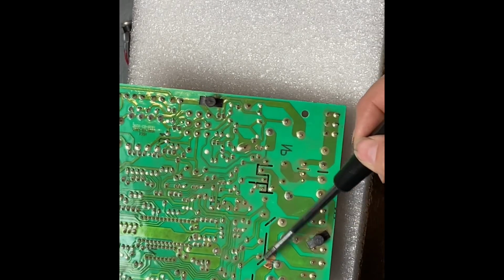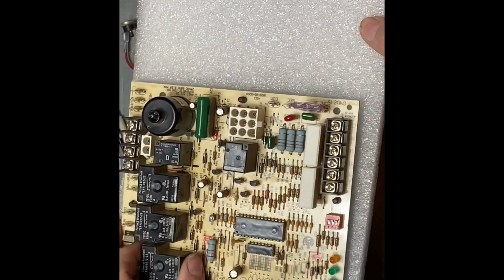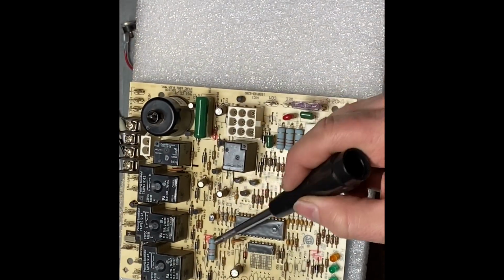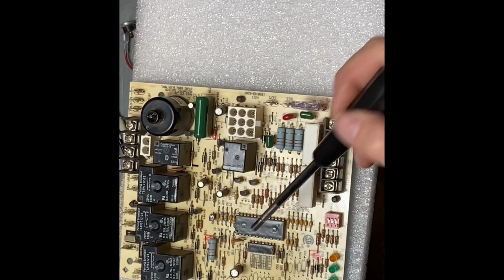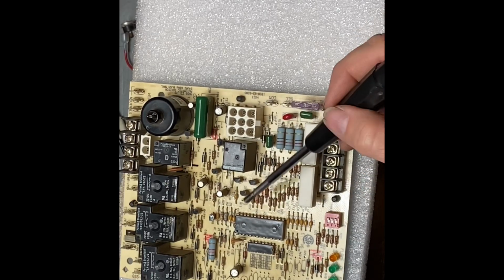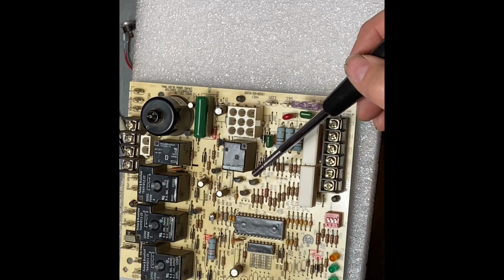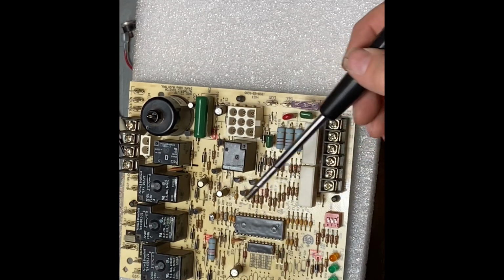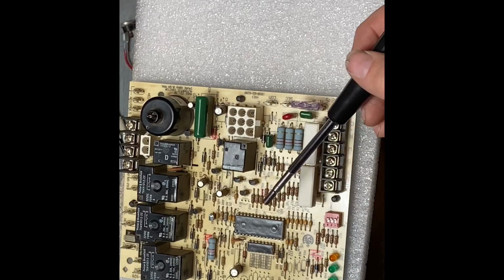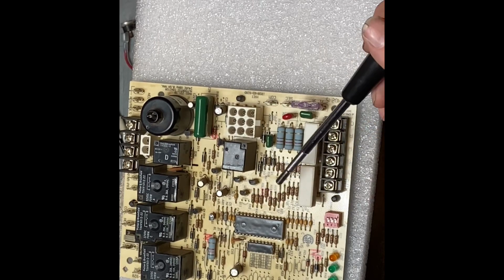So that's one of the things I look for in the back of the board, things like this or any other dark spots here. And I also want to look on the front side of the board to see is there any burnt spots on these boards, and that's a good indication that board is going to need to be replaced. Even if it's working right now, it could be under a certain sequence. It could be a safety component that's going to cause it to not work, and you don't want to go out in the middle of the night to have to go solve that problem.